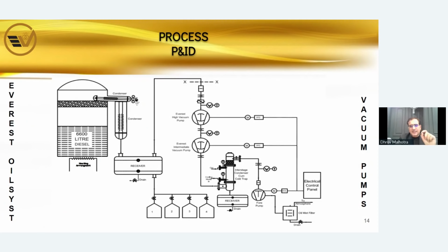But in such cases, we don't mind connecting it with the receiver, the holding tank, which is before the receiver, just for the fact that whatever we are dealing with here are all high boilers. And then you have the typical system on the other side, which I have already shown in the previous photograph as well.